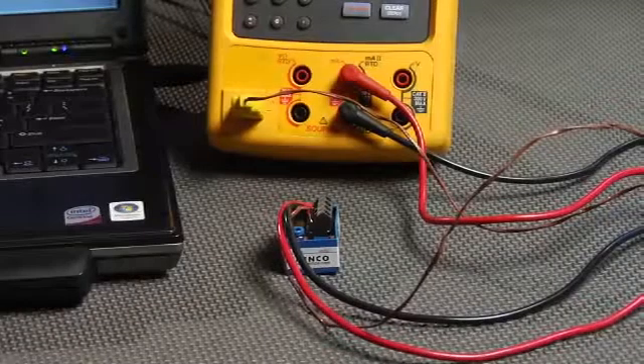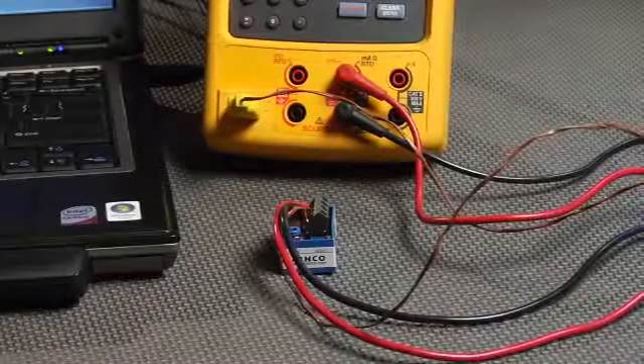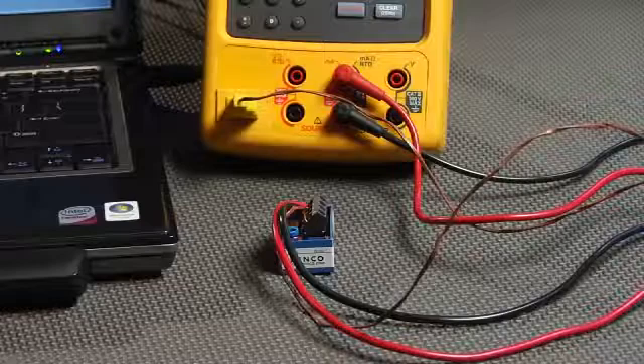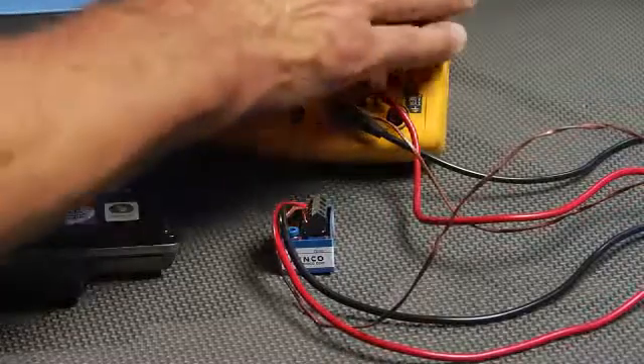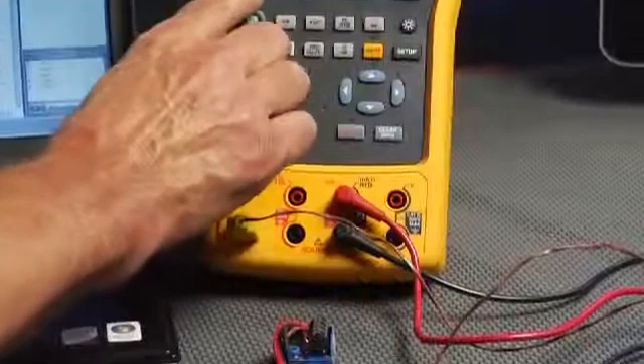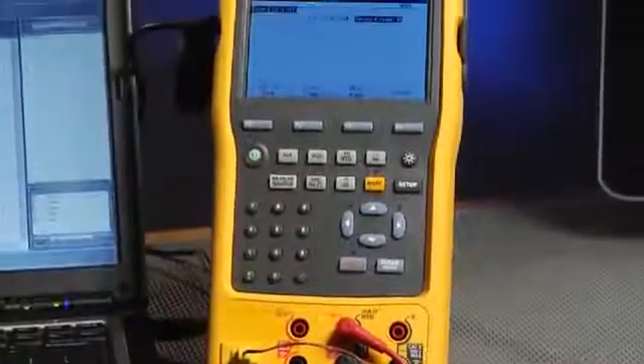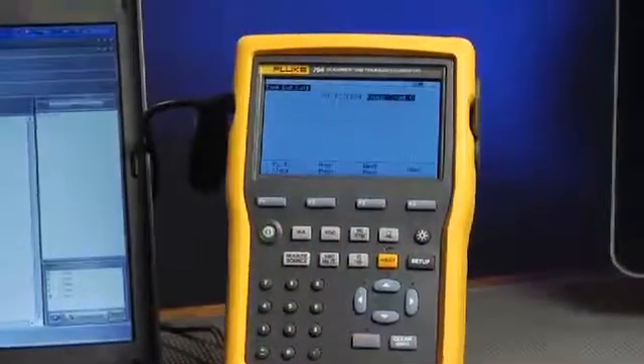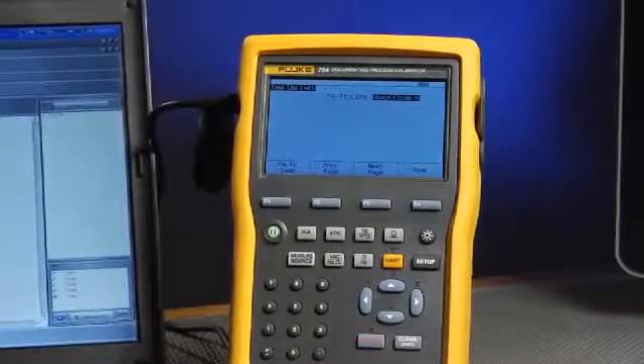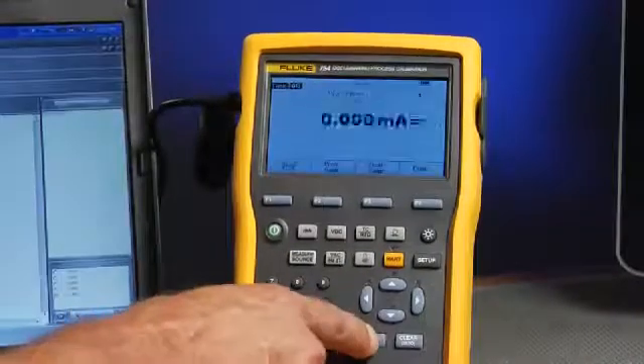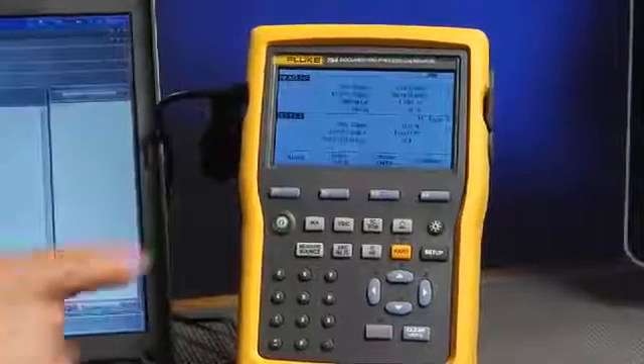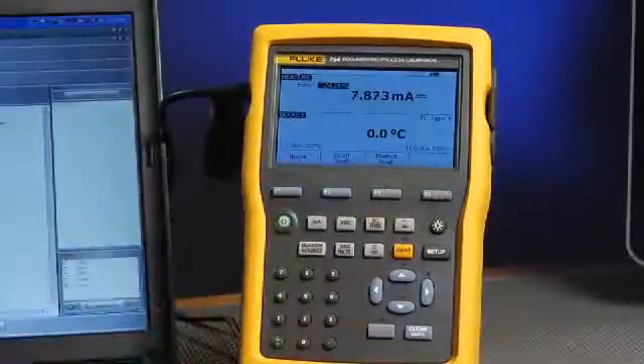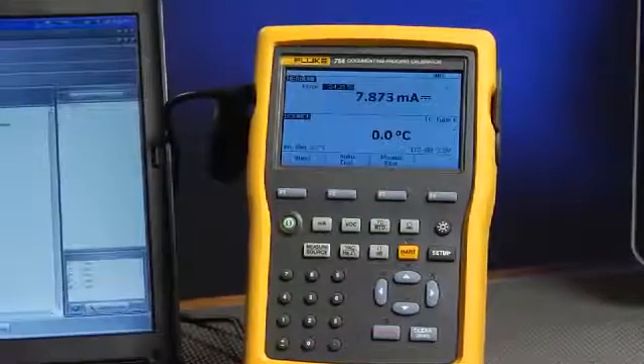Next we're going to select the task loaded into the calibrator. The task is configured for a type K thermocouple transmitter. Select more choices and task. Here you see the task that was loaded into the calibrator from the DPC Track 2 software. Press enter to select the task, and then continue to configure the calibrator for the test.